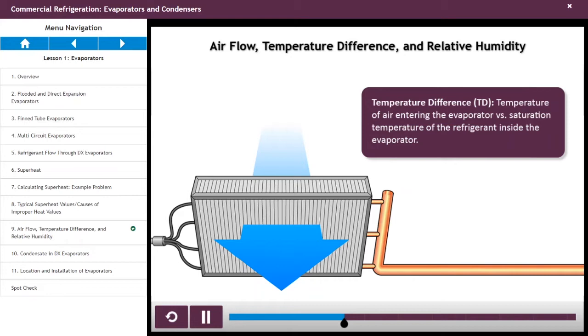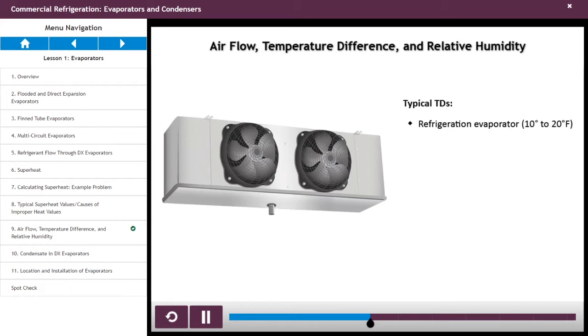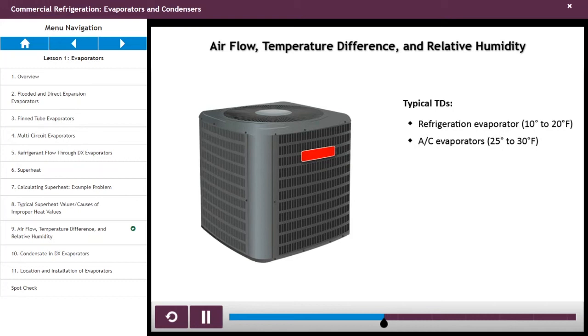The cooling capacity of an evaporator is based on a specific TD. A TD of 10 to 20 degrees Fahrenheit is typical for refrigeration evaporators, while the TD for air conditioning evaporators ranges from 25 to 30 degrees Fahrenheit.